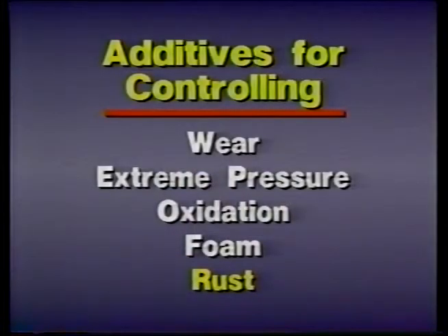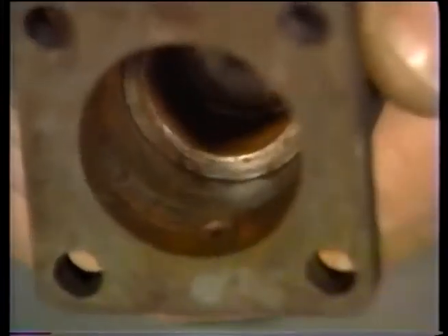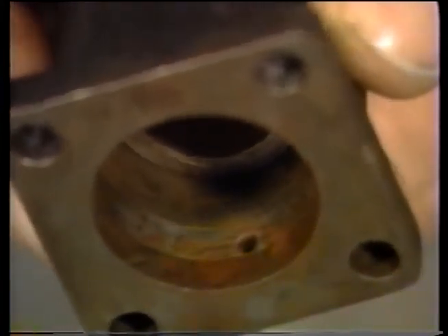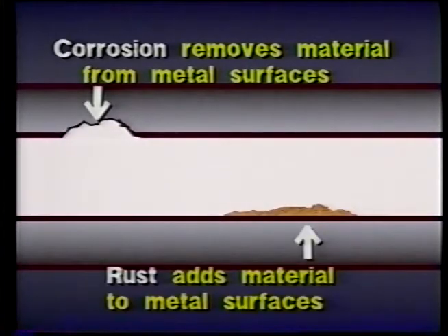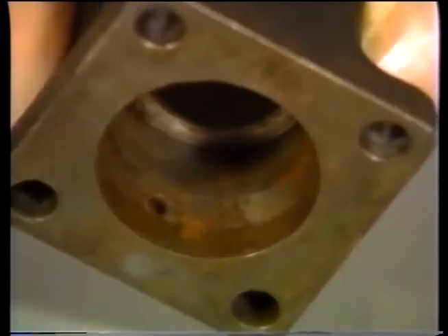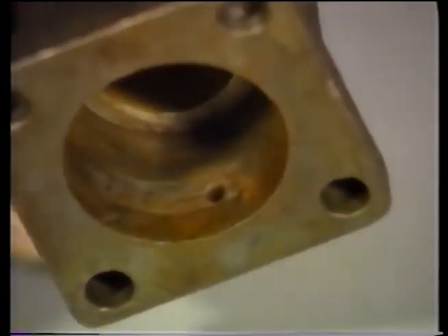Another common problem is rust. Rust may begin to form in a hydraulic system whenever water contaminates the fluid. Rusting is similar to corrosion in that it involves oxidation, but in this case it's the metal parts of the system that are oxidized, not the hydraulic fluid. While corrosion removes material from metal surfaces, rusting adds material and it often interferes with the operation of components. A buildup of rust on the inside surfaces of a valve, for example, may keep it from operating smoothly, and can even prevent it from operating at all.